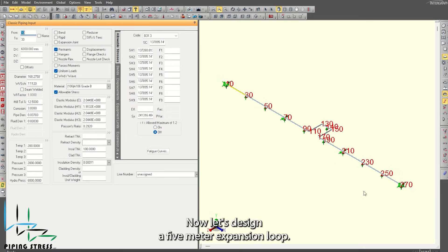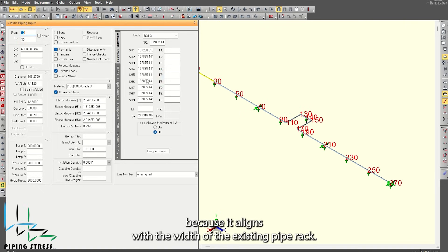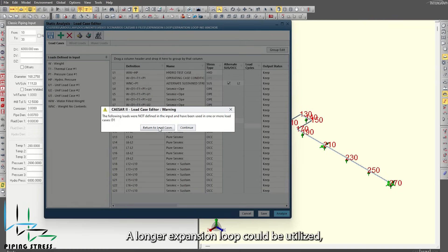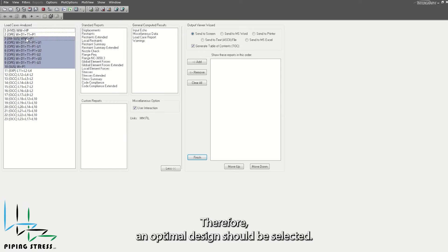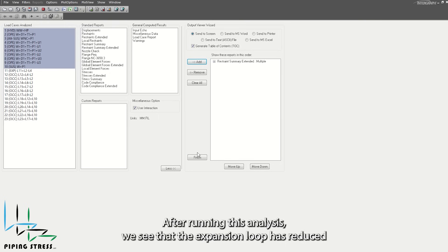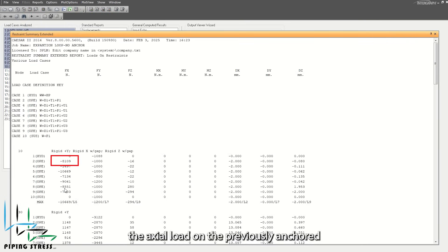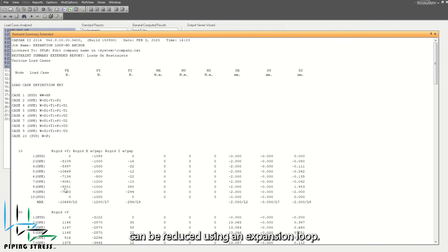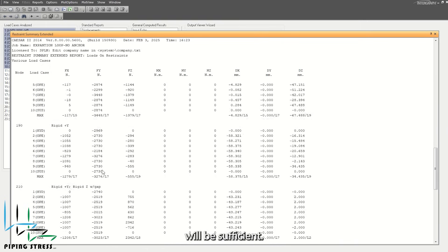Now, let's design a 5-meter expansion loop. The length of 5 meters is chosen solely because it aligns with the width of the existing pipe rack — there is no particular reason for this specific length. A longer expansion loop could be utilized, but it would necessitate additional steel structures. Therefore, an optimal design should be selected. After running this analysis, we see that the expansion loop has reduced the axial load on the previously anchored straight pipe to approximately 9,000 newtons. This demonstrates how much axial loads can be reduced using an expansion loop. Thus, a loop length of around 5–6 meters will be sufficient.